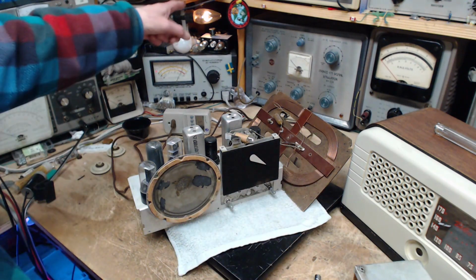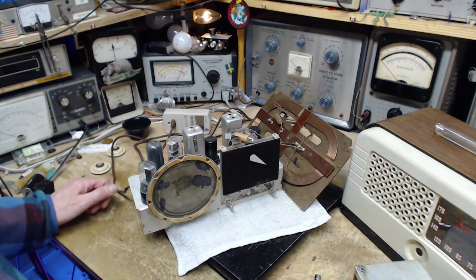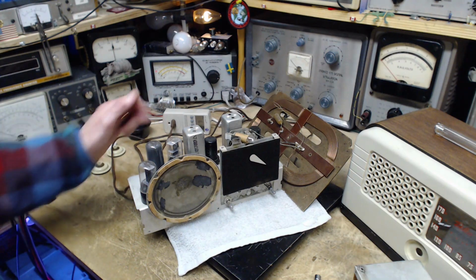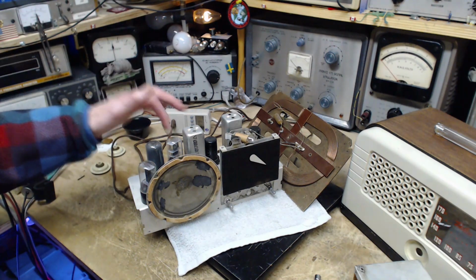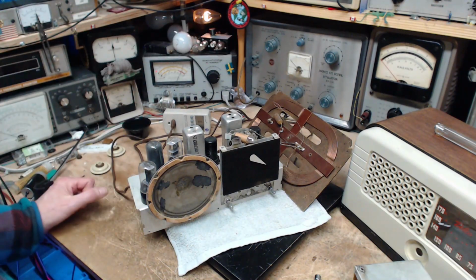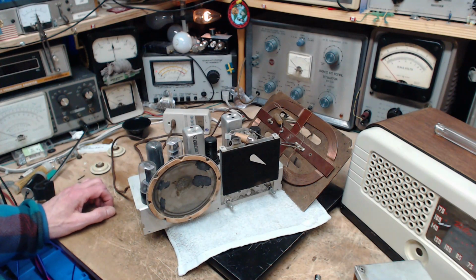If I had not included the light, things would have happened a lot faster. So I can see the element heating up here. You see one of these tubes glowing? They're all working, they're all heating, because if one is out, they're all out - they're in series. Remember those lights on your Christmas tree, and one bulb goes out, the whole string goes out? Same thing.